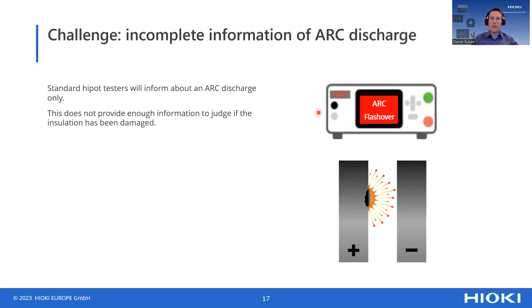So this discharge waveform display will not only show you the arc in terms of a transient here, but it also gives you the post measurement of the parameters later on with very high resolution. And how to do that? Well, ST5680 is not only a Hipot tester per se, but it also features oscilloscope functions. So the capability of having 500 kilosamples per second, recording the data for a longer time in a very fast way, gives the customer the possibility to display the transients and the leakage, what happened when you inject the voltage, and also the current which happens in here, to determine whether the insulation is degraded or not.